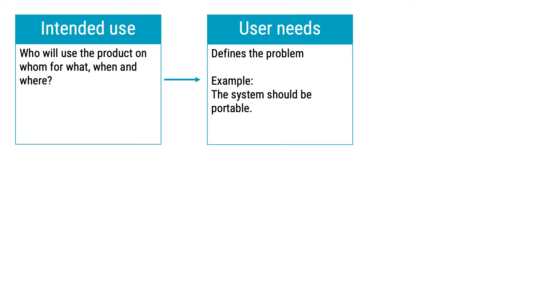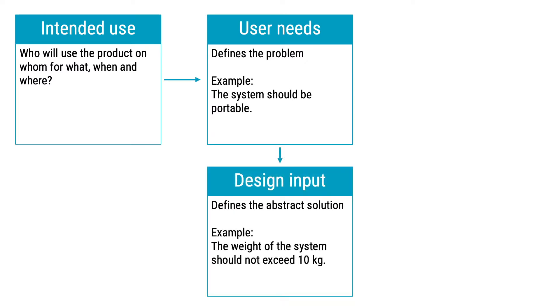Now let's look at user needs. User needs should describe what the users need, and they should be aligned with the intended use. A simple example of a user need is that the system should be portable. User needs should then be translated into design inputs, which are specific technical requirements that realize the user needs when implemented in a design. In this case, portable means that the weight should not exceed 10 kilograms. Getting the translation of user needs into technical requirements right is a really critical thing for the success and customer acceptance of your product.